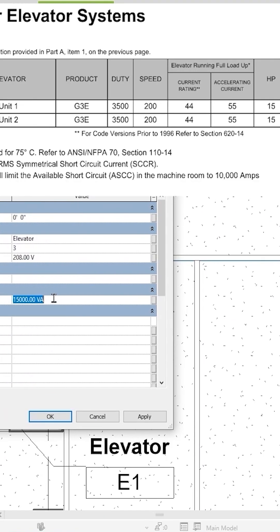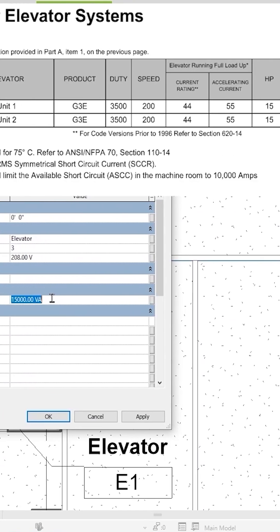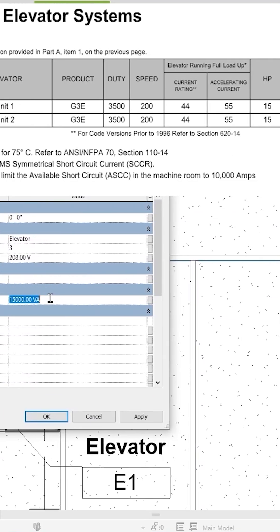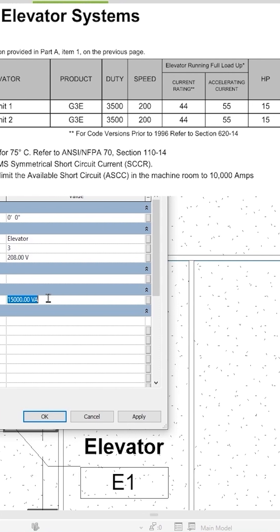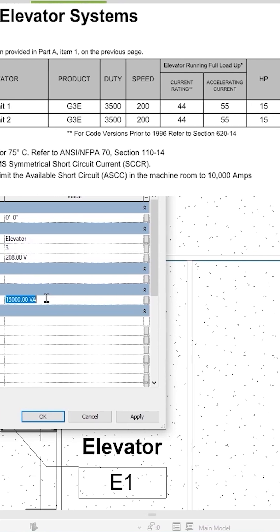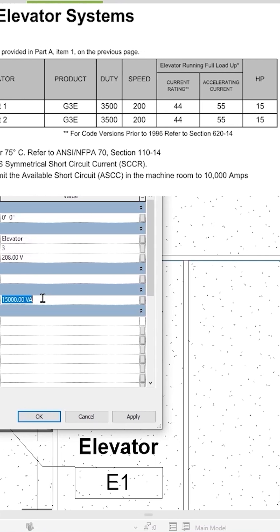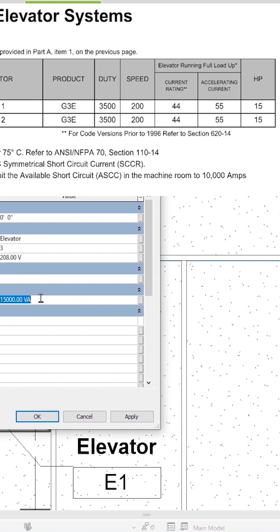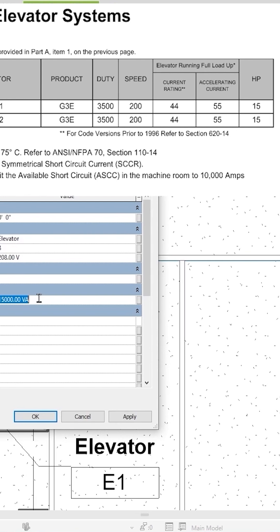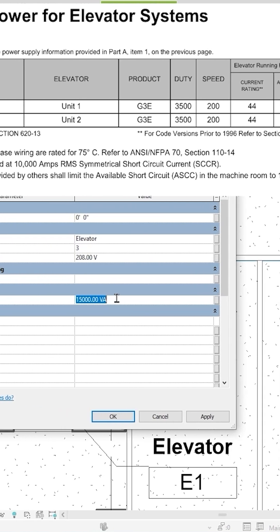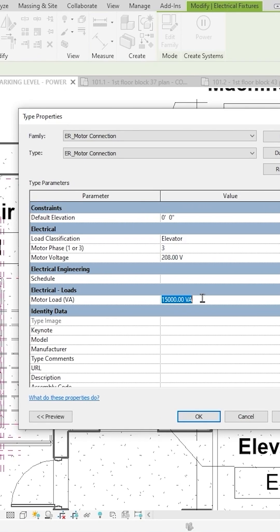Elevators have not just a horsepower rating, but they typically have running load amps and then accelerating amps and things like that. I'm going to base this off the accelerating worst case amps of 55 amps. If I don't know how many VA that is, I can insert a formula in here.